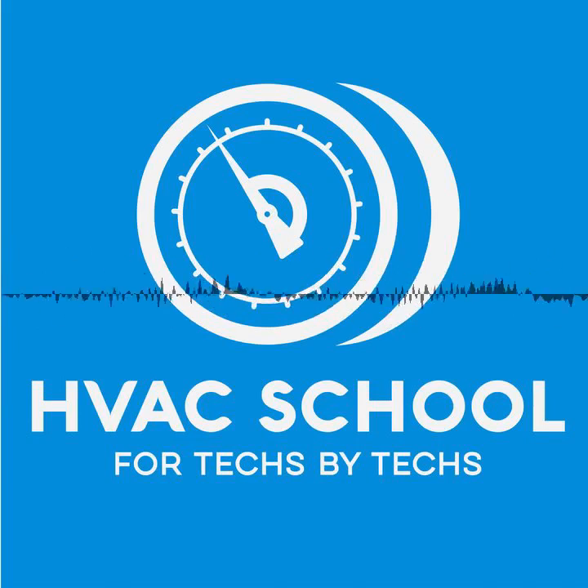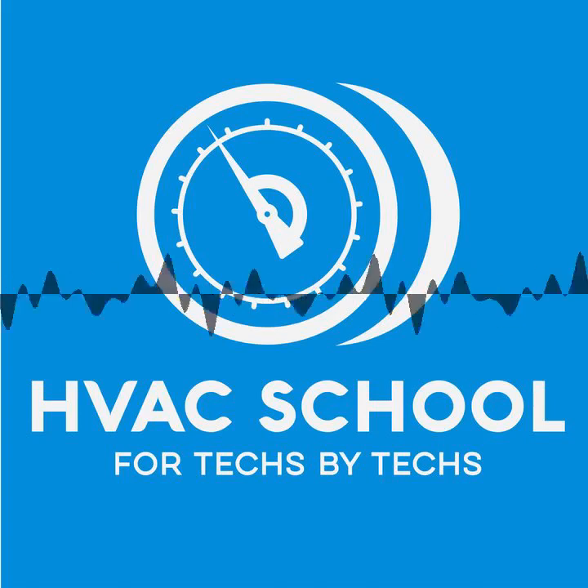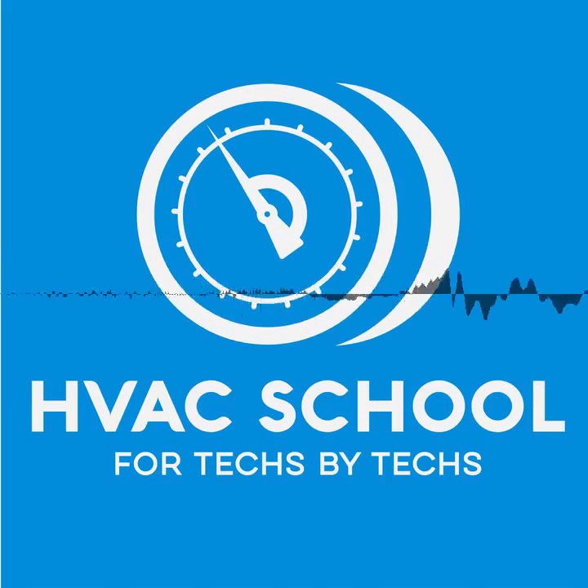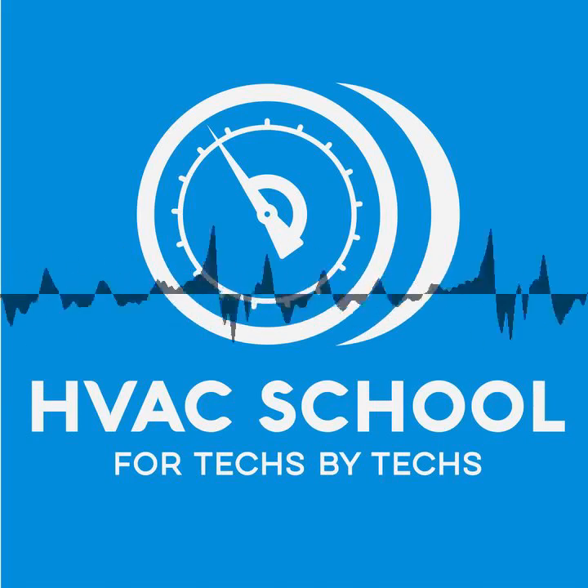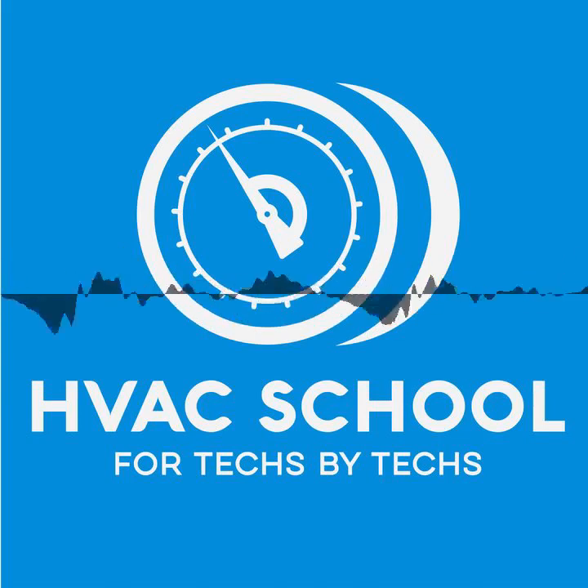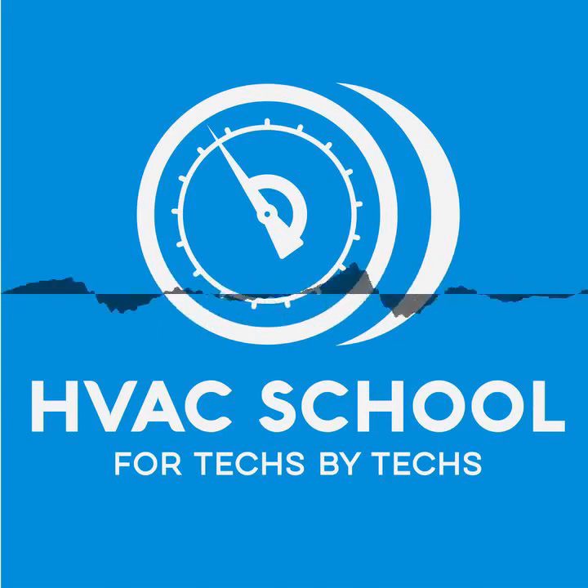Now, here's why you don't want to get done brazing and then pressurize the system without doing a purge through. The reason is just like if any of you guys have ever used an air compressor, when you compress air and increase its density, or compress nitrogen and increase the density, what's the moisture do in the air, Brian? Answer is it condenses, Jim. It condenses to a liquid. And typically in an air compressor, that's why we drain the air compressor out. We drain the moisture that's condensed in the bottom of an air compressor.